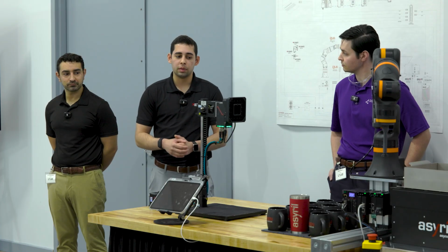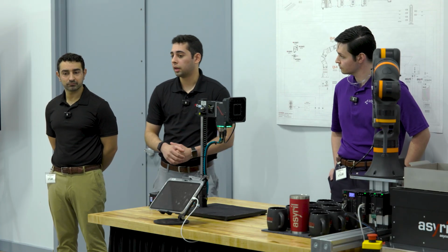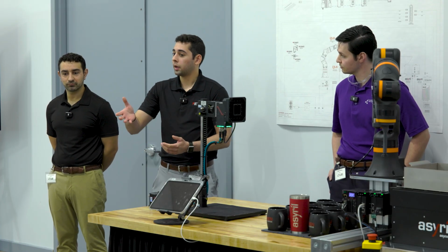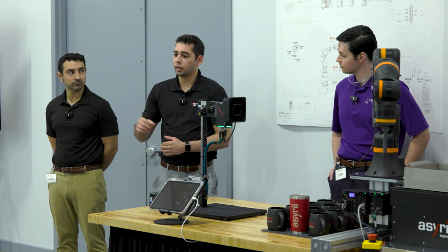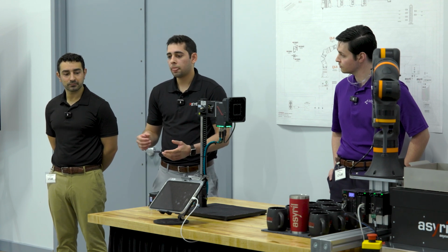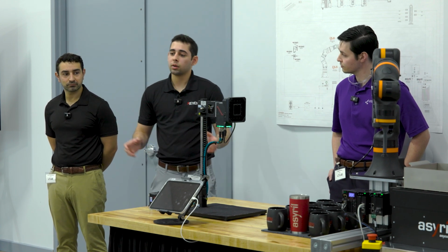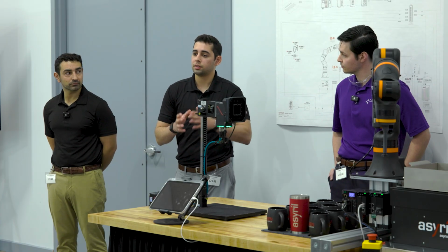The third option would be we can put a record button on an HMI. So even on your PanelView, you can put a record button on there so that when the operator sees that there's a fault, they go hit this button. Now we're saving on an SD card the last 10 minutes of data.